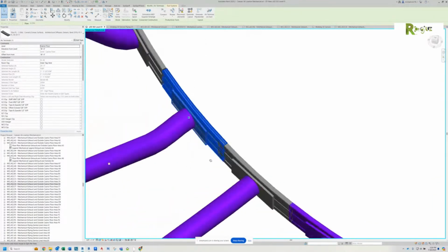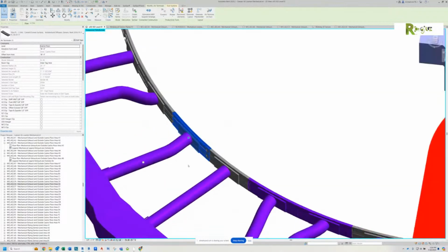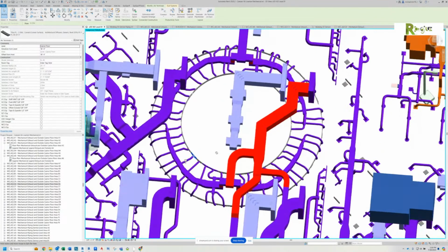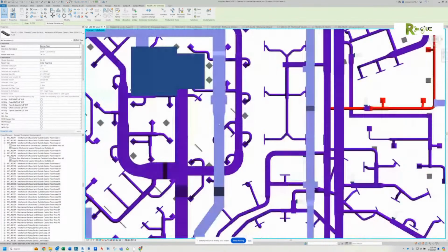The gray ones are the architectural ones. That's the one where they thought they had 40 of those, where they only have 38. And then around the outside, there's 53 of them. But you have to be a little bit careful, because some of them they have as return diffusers. That one right down there where your arrow was, that's a return diffuser.